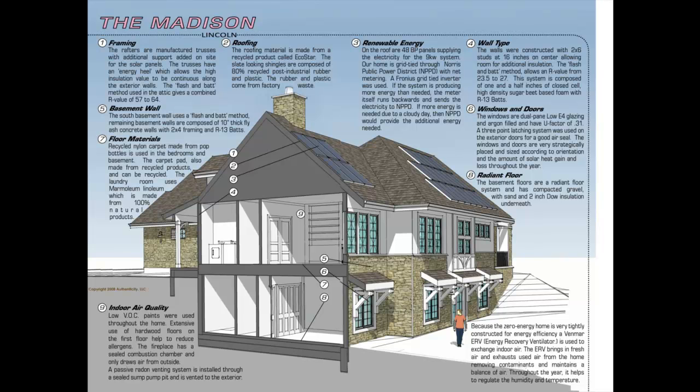The other thing Mike Rizak did was put in an air exchanger, so there's a constant volume of air being exchanged in the home. I think he said at the start they have about a third air change per hour. You're required to have a certain amount of air because of the tightness of the home. You need mechanical ventilation, and that comes through the furnace, so it's filtered air. The actual air quality of mechanically ventilated homes is often better, because it removes the allergens and other things that might lead to problems.